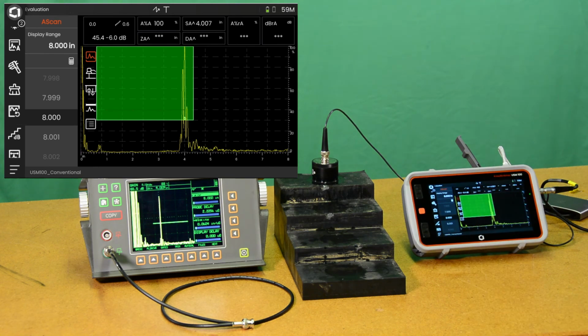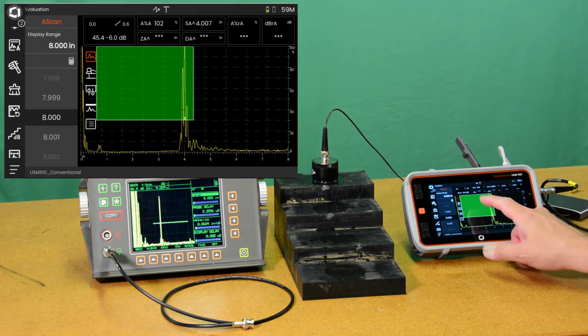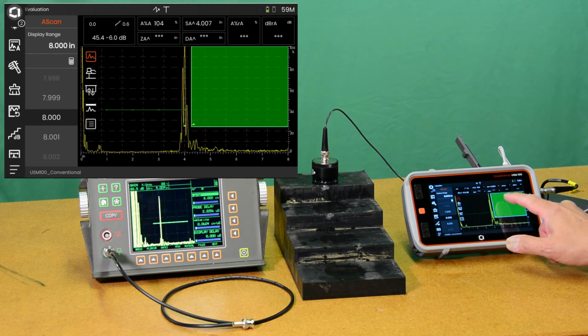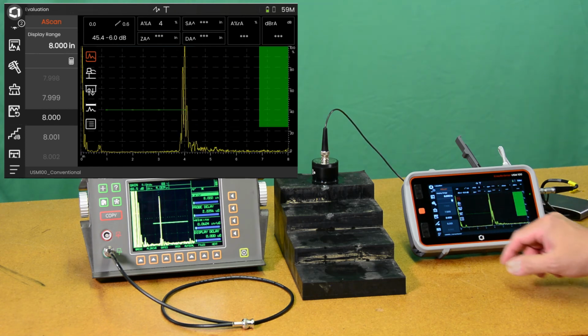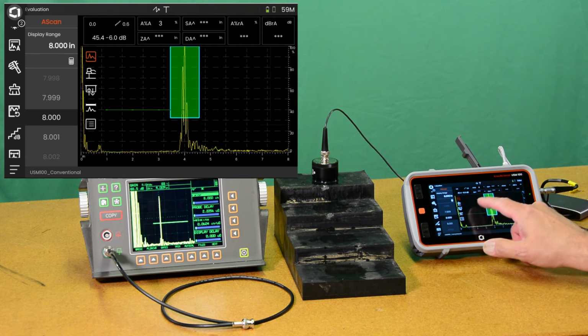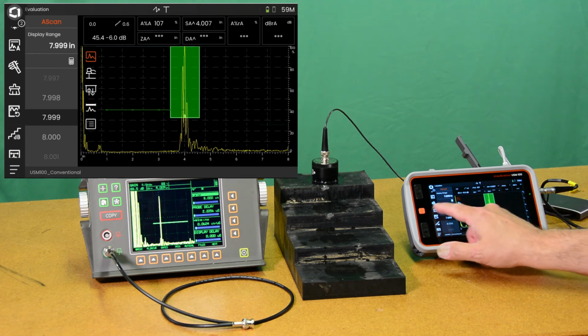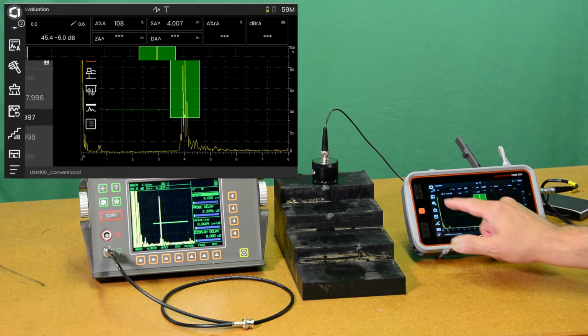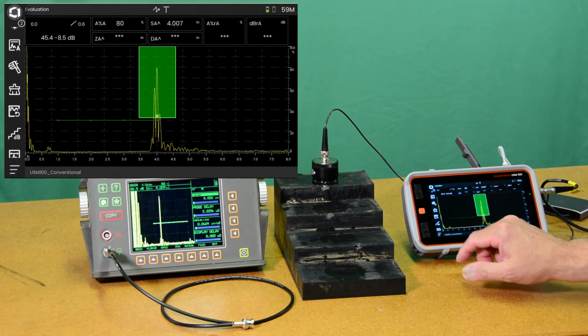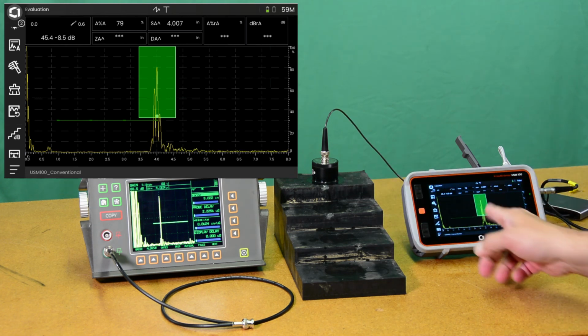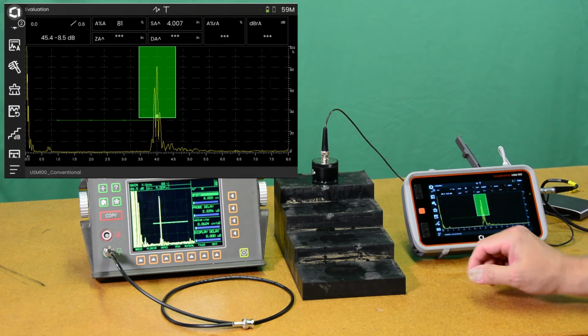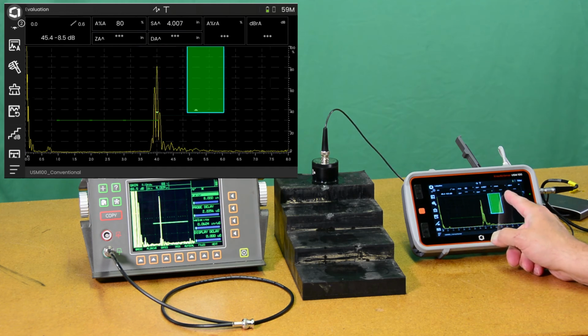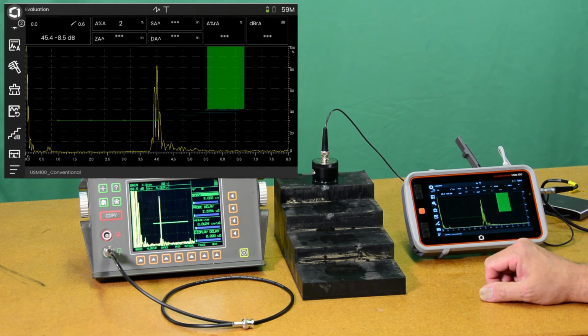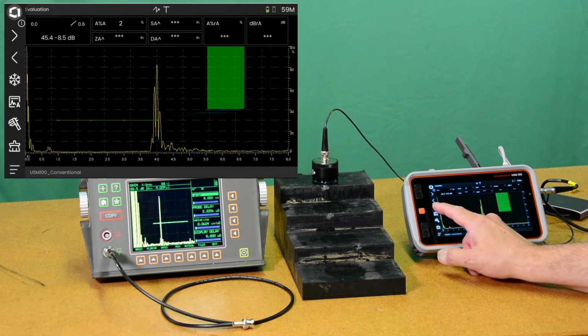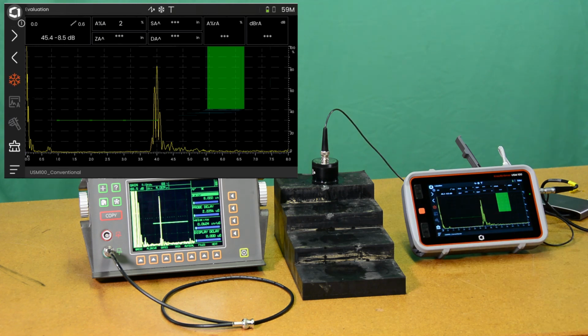Okay, there we have, sort of an apples to apples comparison. Move our gate out of the way here so that you can see the echo nicely. Actually, let me bring that back here a second. Hide the menu. Oops. Hide the menu. Do an auto 80. Now we have apples to apples. 8 inches of range, just like on the 60. We have our echo at 80%. We're running live. I can scroll down here, hit the freeze button, and freeze that. So there's a good side-by-side comparison.